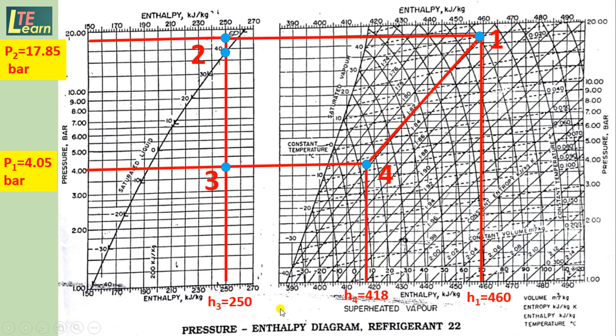So here you see the suction pressure line, and this is the discharge pressure line, which are drawn horizontally. As per the temperature readings, after compression is point number 1, after condensation point number 2, after expansion point number 3, and after evaporation point number 4. Using these temperatures, we locate these 4 points. After that, through these points we project lines vertically onto the enthalpy scale. So we find from this line enthalpy H1, from this line enthalpy H4, and from this line enthalpy H3.